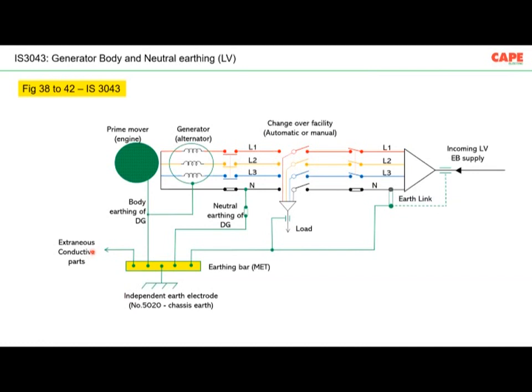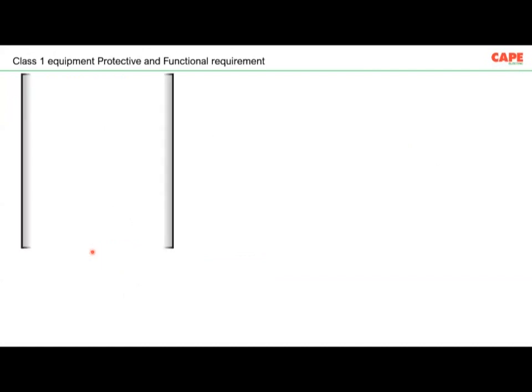As I said, earthing is a very, very important subject. If earthing is wrong, or if you make a mistake in your earthing, the building can be in a very dangerous situation. But you must also understand that an electrical installation will work without an earthing as well. Then what is the purpose of earthing? Earthing is to ensure that your installation is safe during an insulation failure, or during a surge, or during lightning, or during some events. So in a normal condition, your electrical installation will work even without earthing. So whatever we are doing in the name of earthing is required only when there is a critical situation.